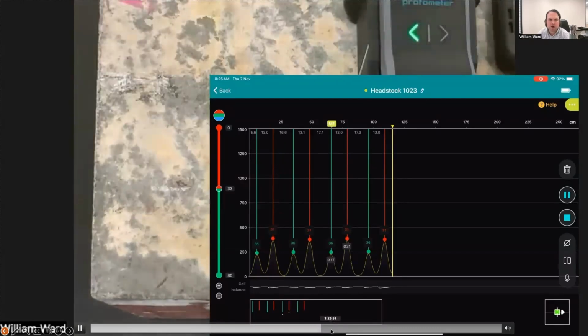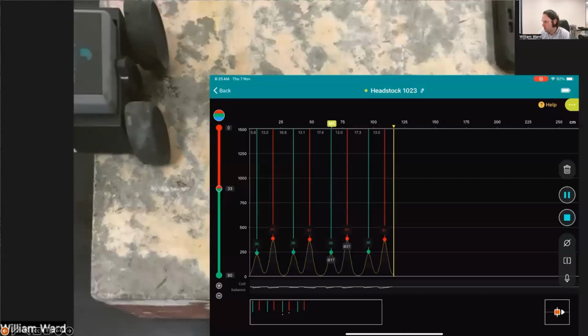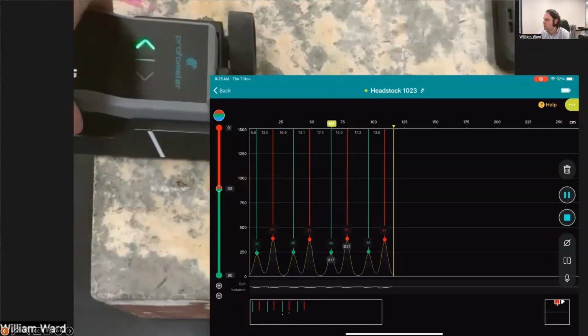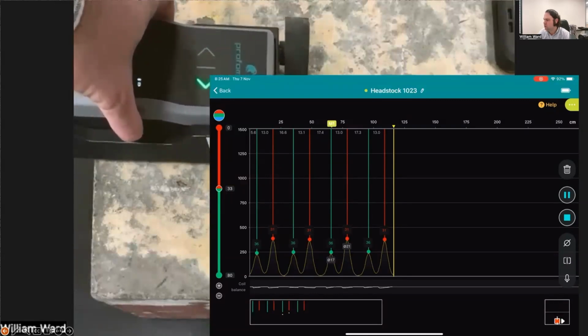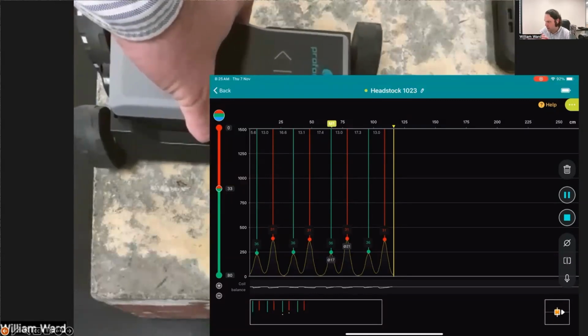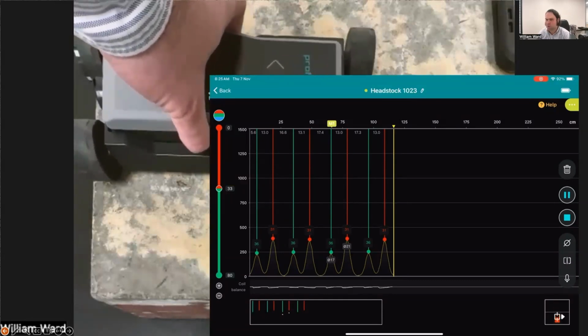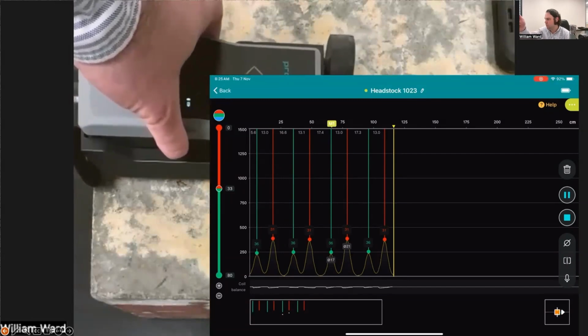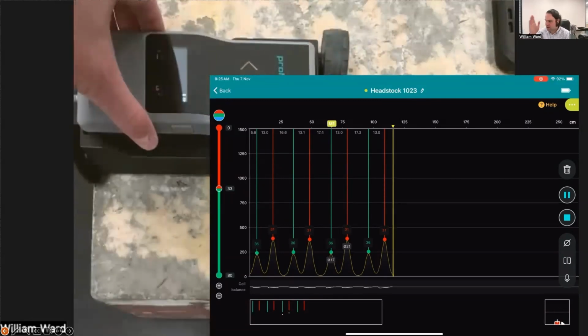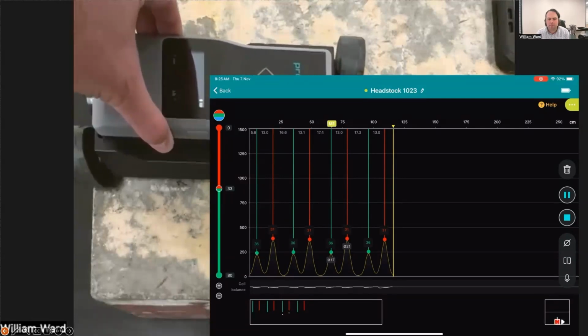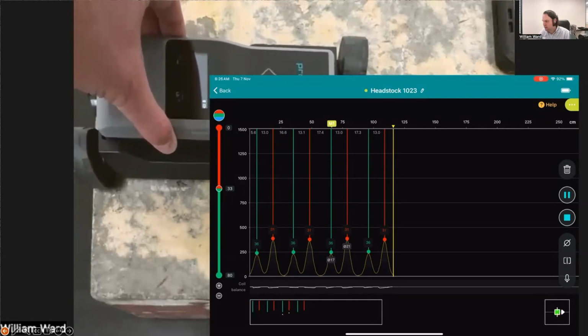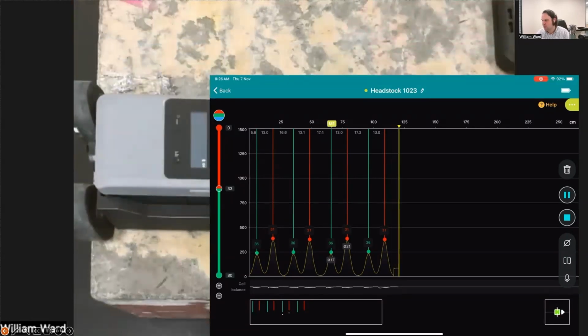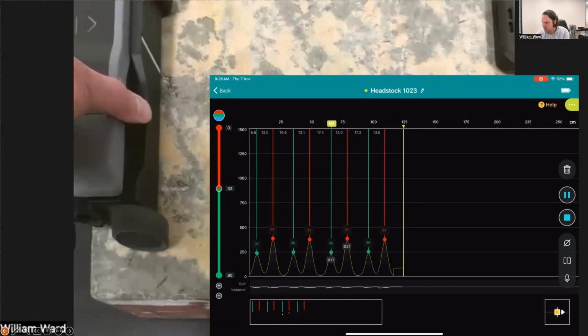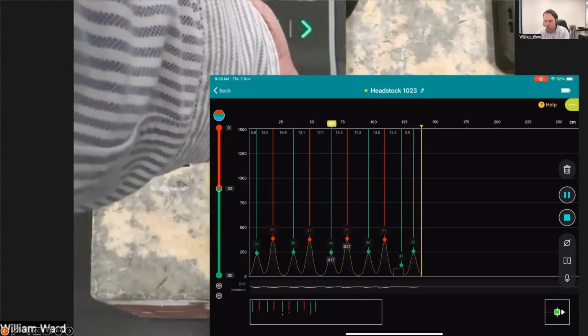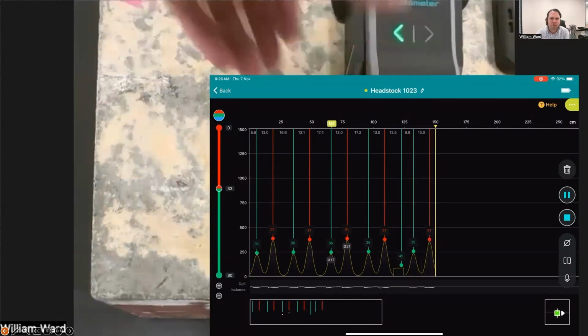Now, look in the bottom right corner for me, please. That green box that varies to red and starts to move around, that is a coil balance box. If I'm too close to a bar above or below the path I am rolling, that bar will go red and it will move towards the position of that bar. So pulling the cover meter back towards yourself until you are centered in the middle of the top, higher and lower bar, and then can roll over the bars you're perpendicular to, will ensure precision in your measurements. So do be aware that you have a visual representation of coil balance, so top and bottom balance, in the PM8000 and PM8000 Pro configurations.